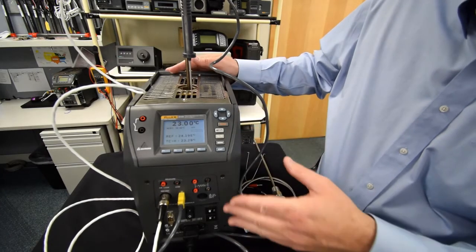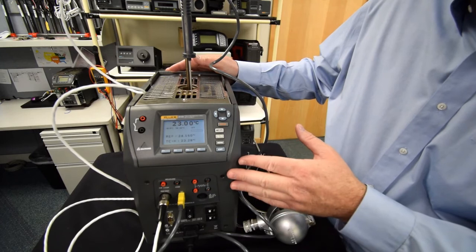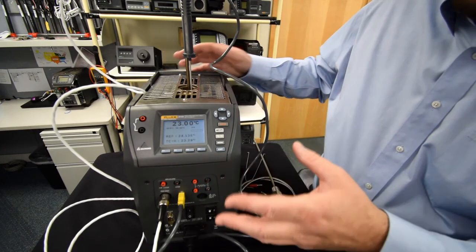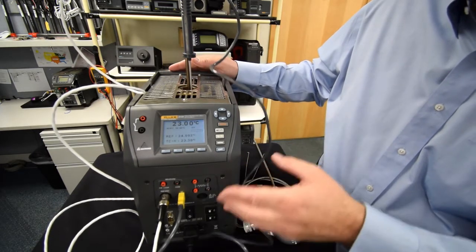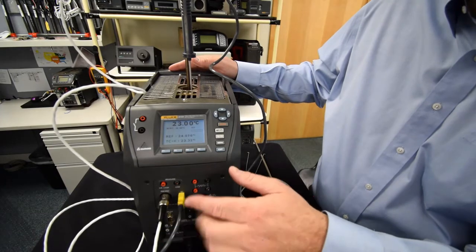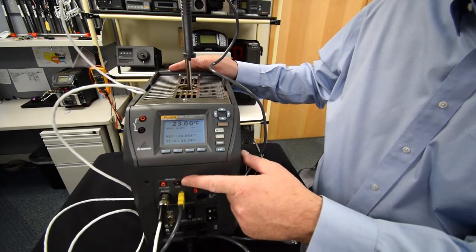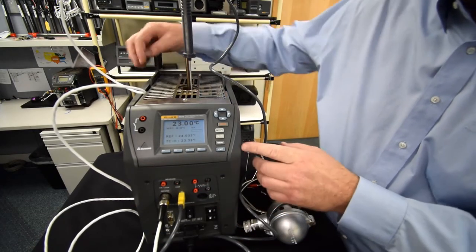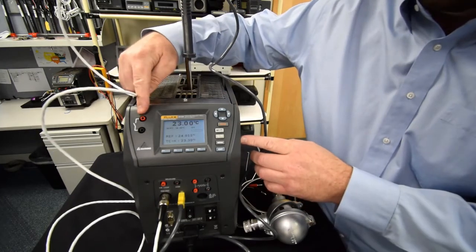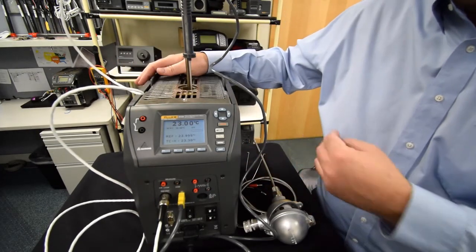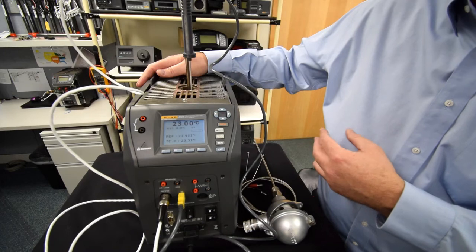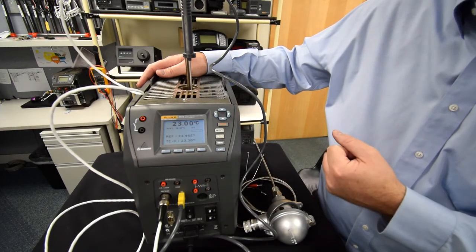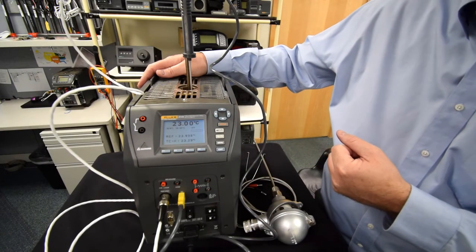So again, great all-in-one unit if you're out in the field and a technician where you've got multiple things you may be testing either from RTDs to thermocouples or even if you need to drive a 4 to 20 milliamp circuit. It's also got this switch test indicator. So it does capture the state of a switch test whether it's open or closed or when it does open or close so you can capture that dead band.